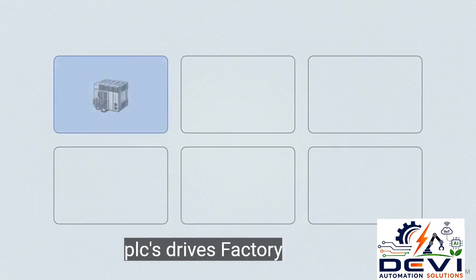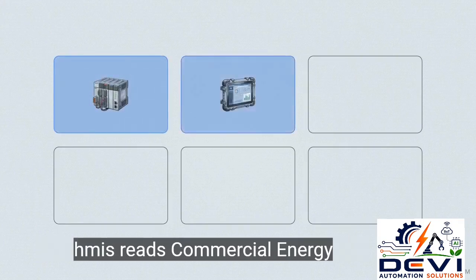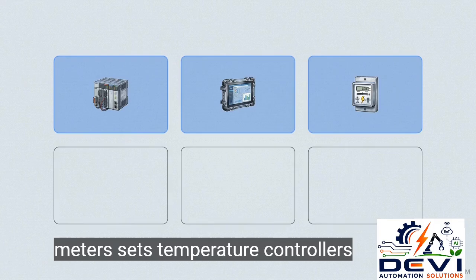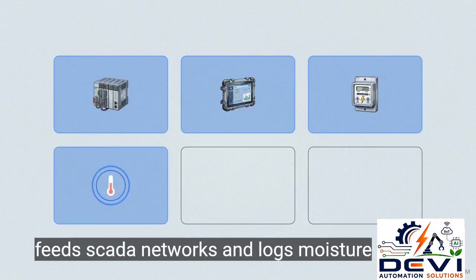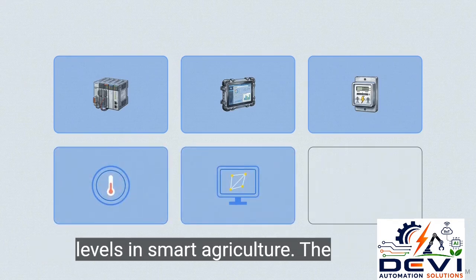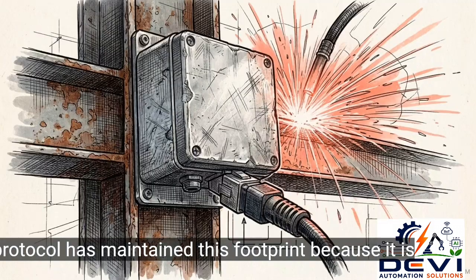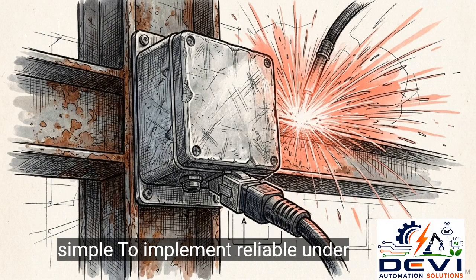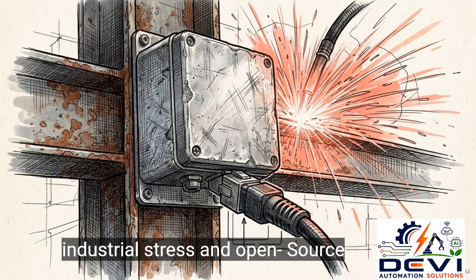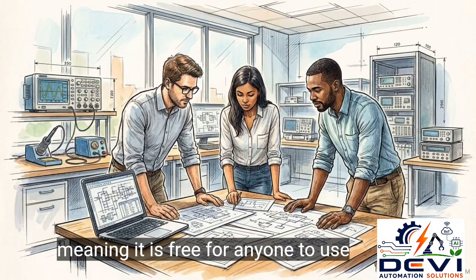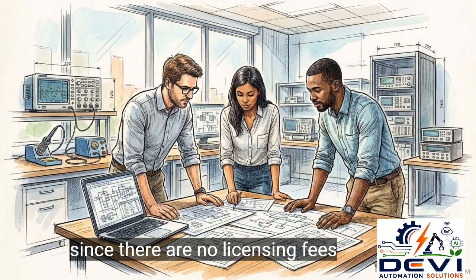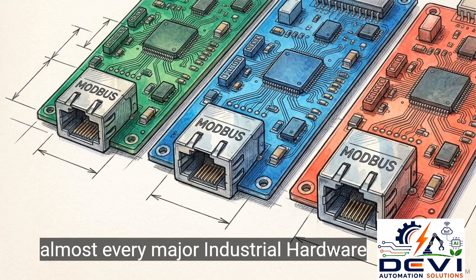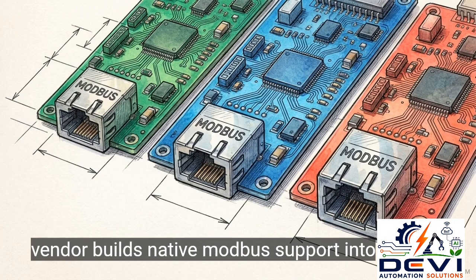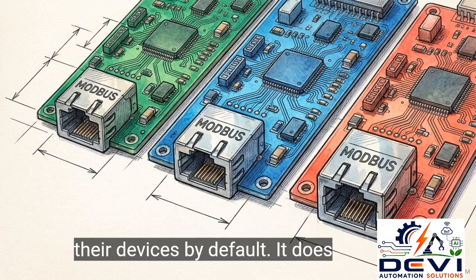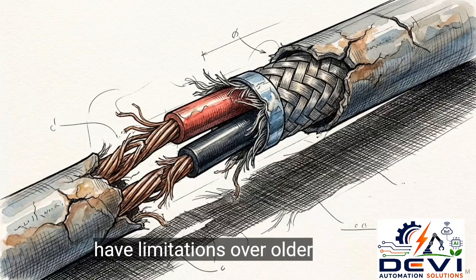As you can see in this application grid, it manages data for PLCs, drives factory HMIs, reads commercial energy meters, sets temperature controllers, feeds SCADA networks, and logs moisture levels in smart agriculture. The protocol has maintained this footprint because it is simple to implement, reliable under industrial stress, and open source, meaning it is free for anyone to use. Since there are no licensing fees, almost every major industrial hardware vendor builds native Modbus support into their devices by default. It does have limitations.